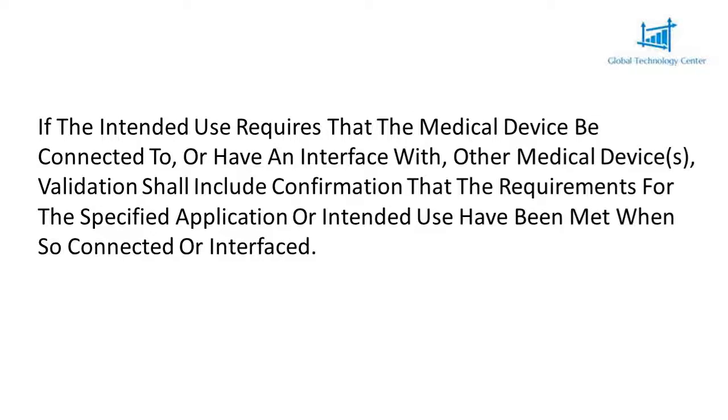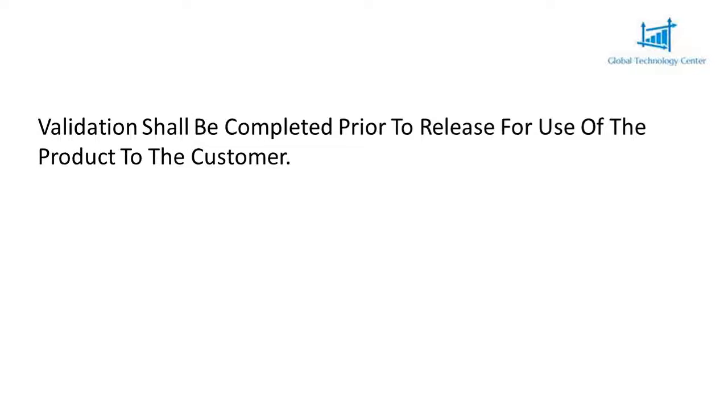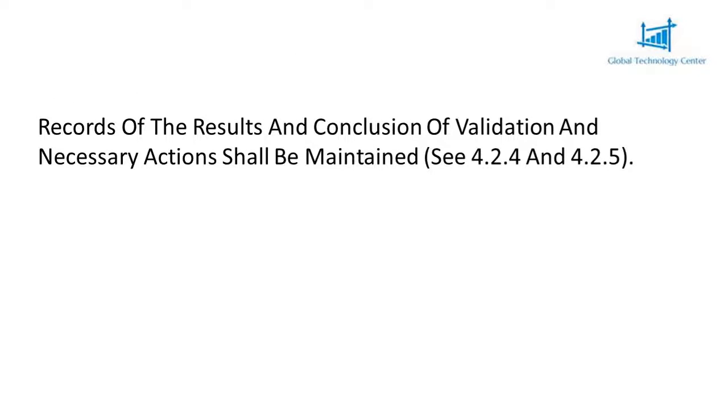If the intended use requires that the medical device be connected to, or have an interface with, other medical devices, validation shall include confirmation that the requirements for the specified application or intended use have been met when so connected or interfaced. Validation shall be completed prior to release for use of the product to the customer. Records of the results and conclusion of validation and necessary actions shall be maintained.